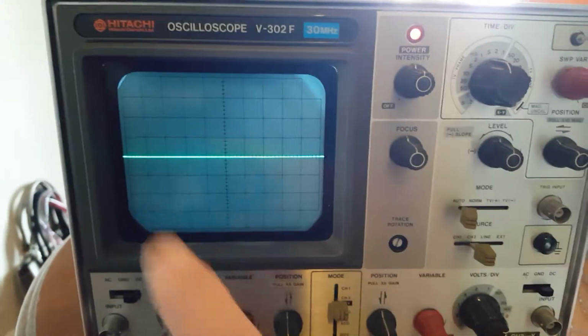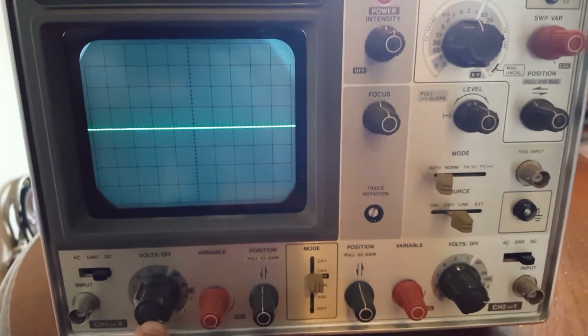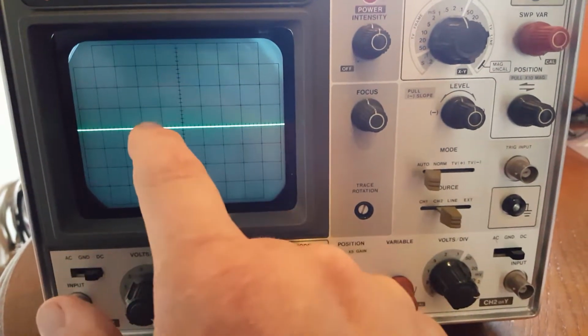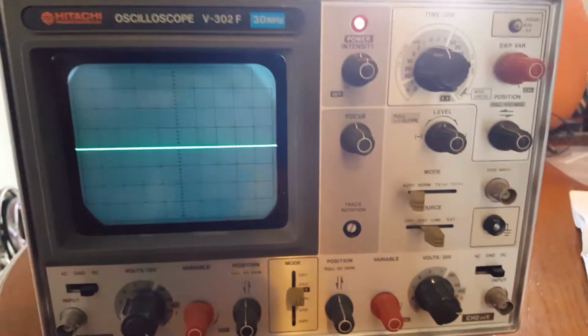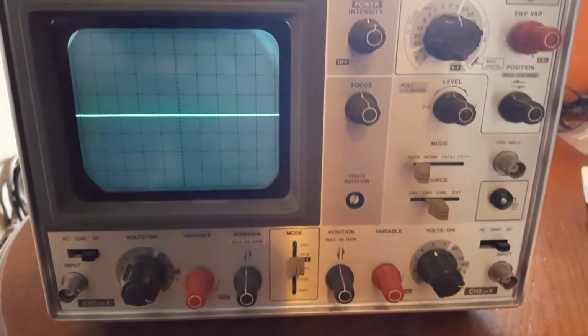So again, if your trace, when you flip from 5 millivolts to 10 millivolts, is off by more than a tenth, you just adjust the little blue pots until it only moves about a tenth.